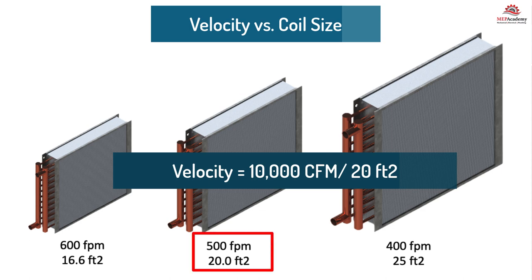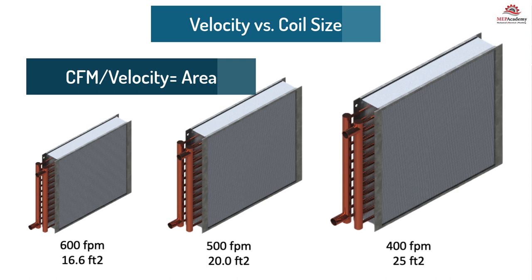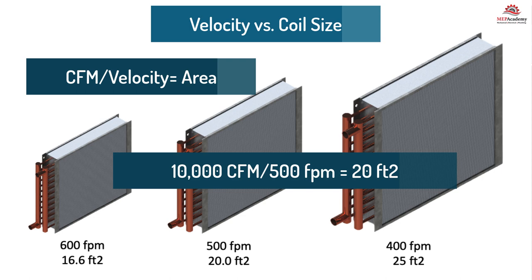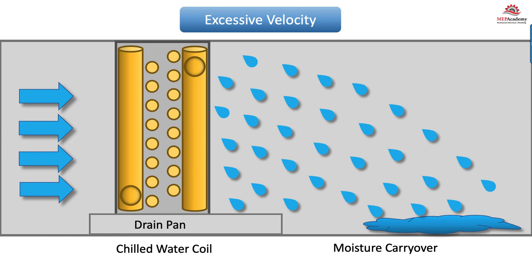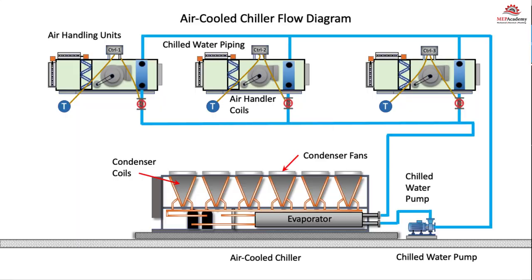We can also use this formula to determine the required face area of the coil by taking CFM and dividing it by velocity. Face Area (sq ft) = CFM ÷ Velocity (FPM). For example, 10,000 CFM ÷ 500 FPM = 20 sq ft face area. If velocity is too high, condensate can be blown downstream of the drain pan. Moisture carryover can leak out of the ductwork and cause damage to the building or within the air handler.